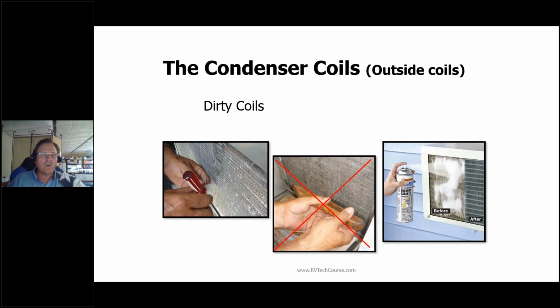The outside coils are just like the inside coils. They need to be clean. Now, on the left-hand picture, the little red handle device is called a fin comb. It basically is like a comb that you run through your hair. Say you pull down through a residential area and a tree branch scrapes alongside and bends those fins over, what you've just done is affected the efficiency of that air conditioner's coils.